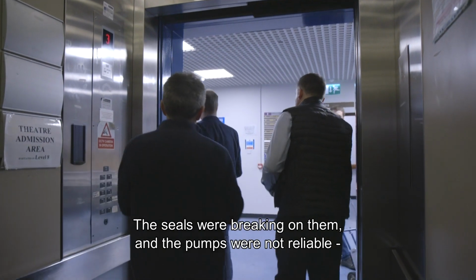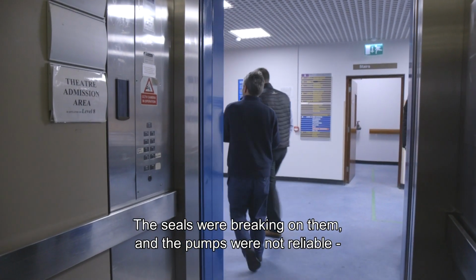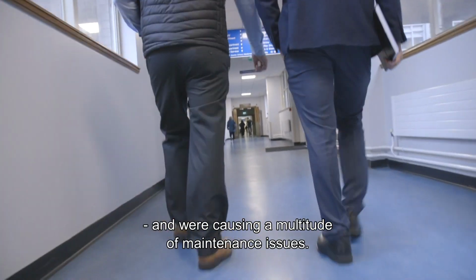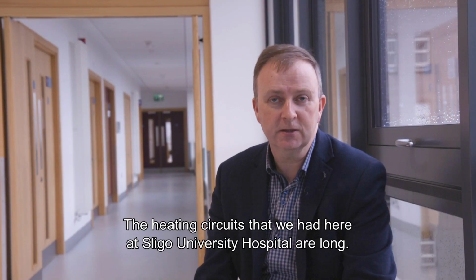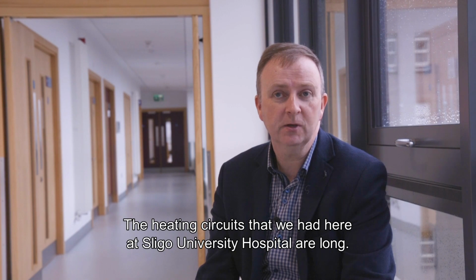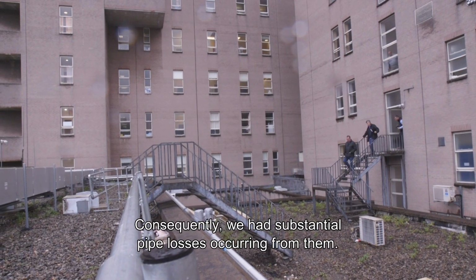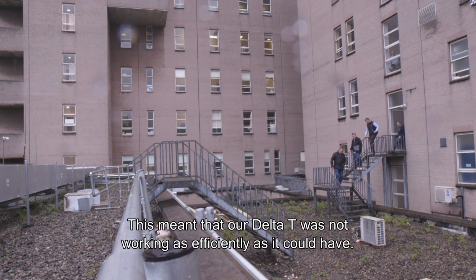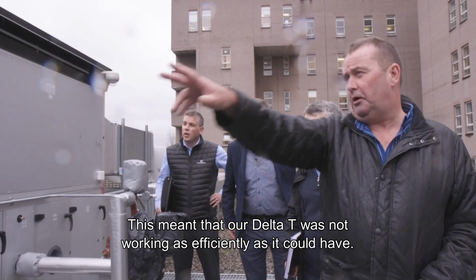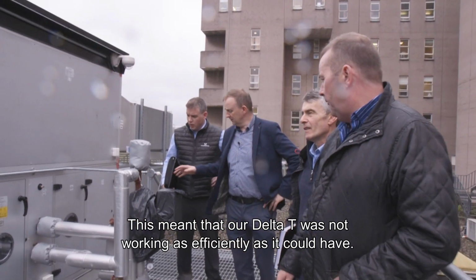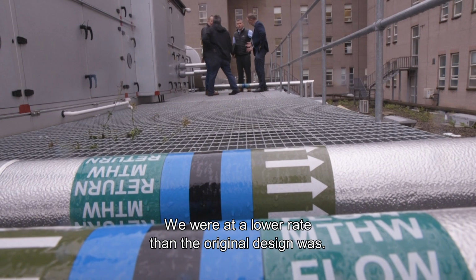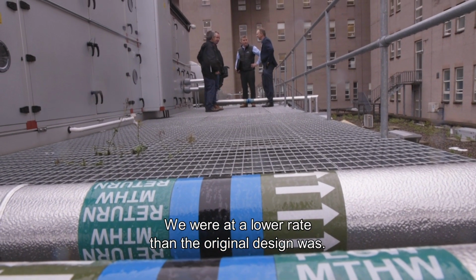The seals were breaking on them, and we were finding that the pumps were not reliable and were causing a multitude of maintenance issues. The heating circuits that we had here at Sligo University Hospital are very long. Consequently, we had substantial pipe losses occurring from them. This meant that our Delta T was not working as efficiently as it could have been. We were at a lower rate than the original design was.